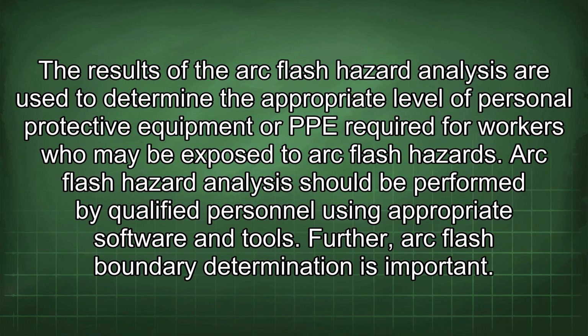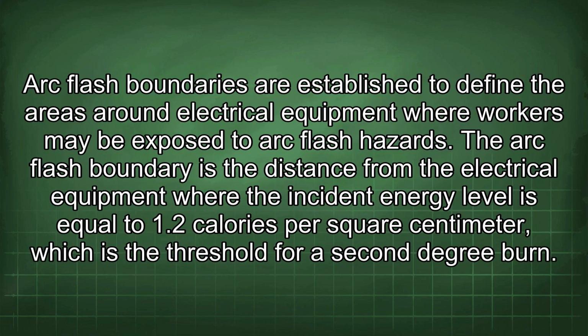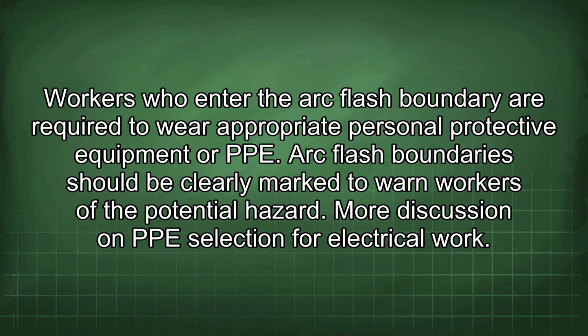Arc flash boundary determination is also important. Arc flash boundaries are established to define the areas around electrical equipment where workers may be exposed to arc flash hazards. The boundary is the distance from the equipment where the incident energy level equals 1.2 calories per square centimeter, the threshold for a second-degree burn. Workers who enter the arc flash boundary are required to wear appropriate PPE, and boundaries should be clearly marked to warn workers of the hazard.